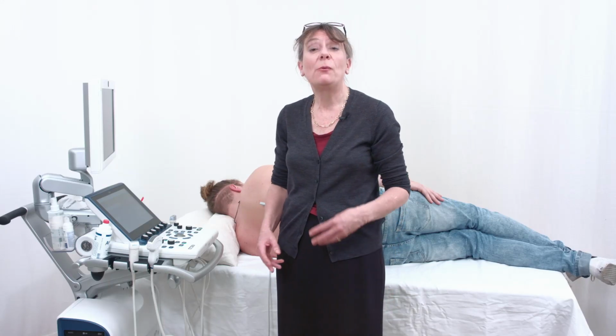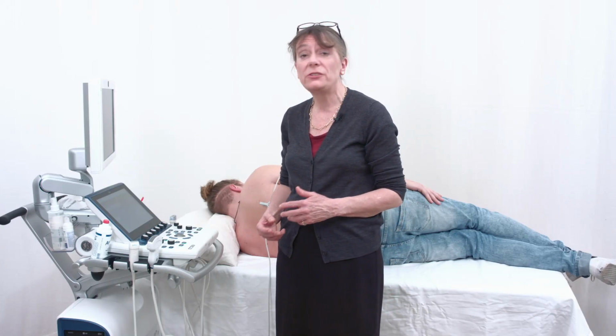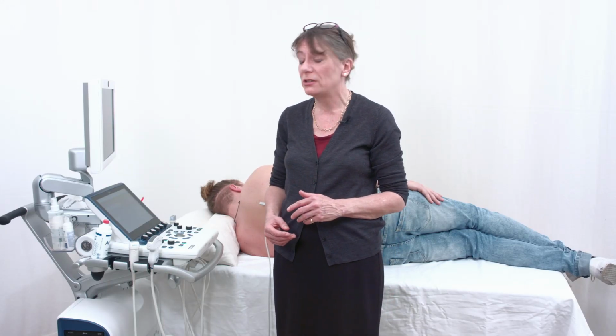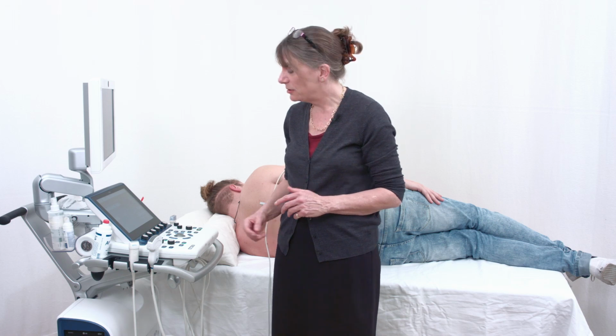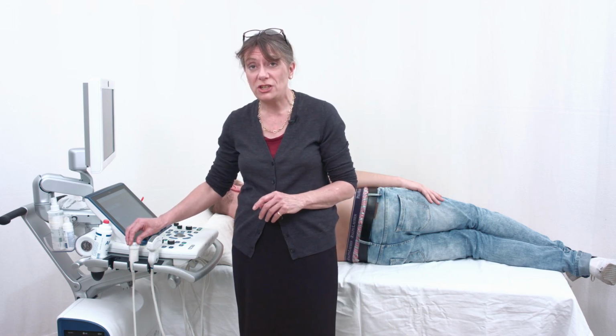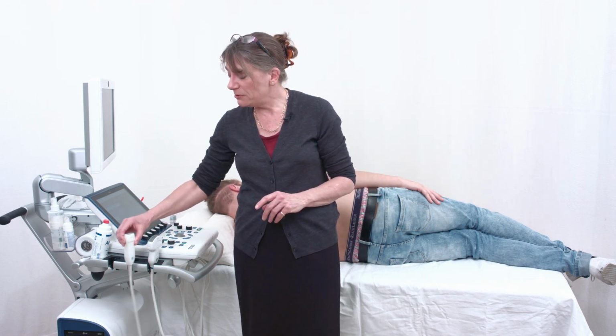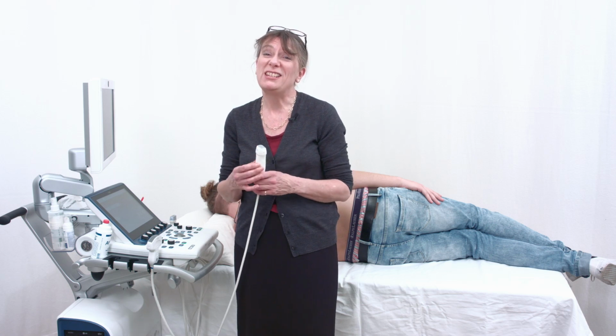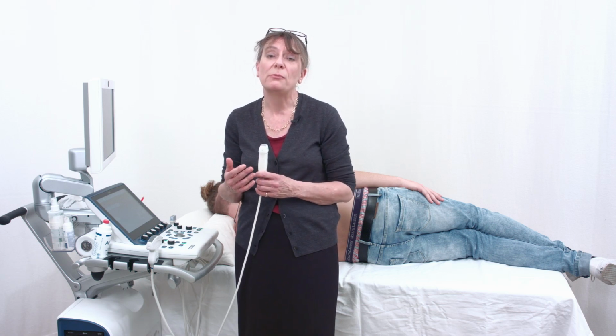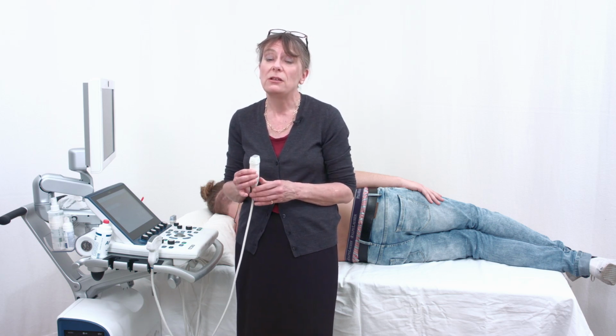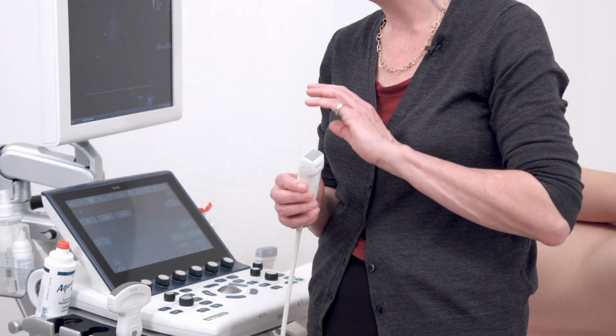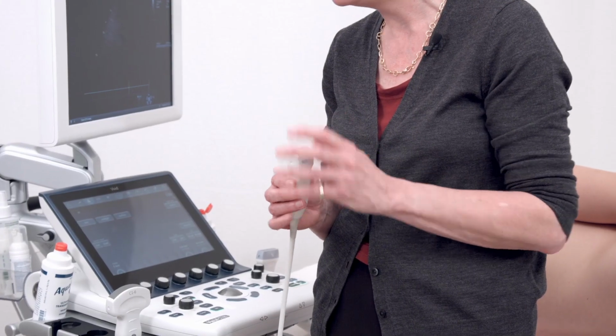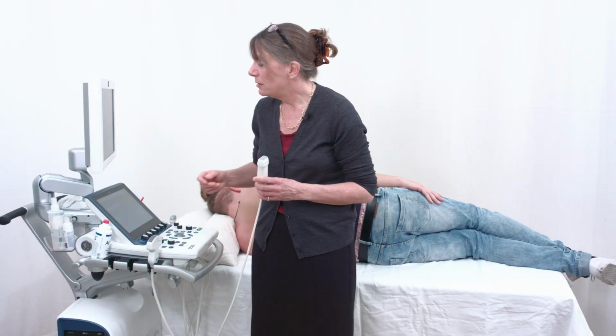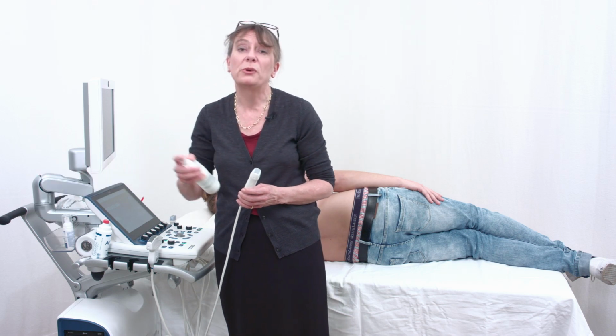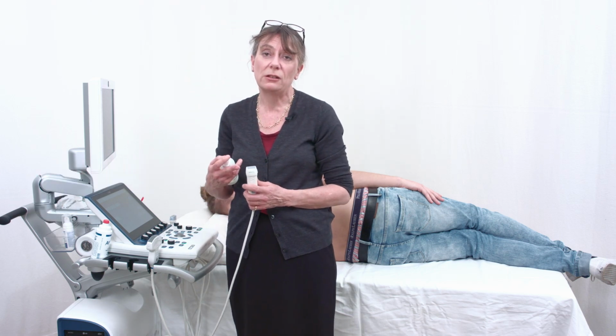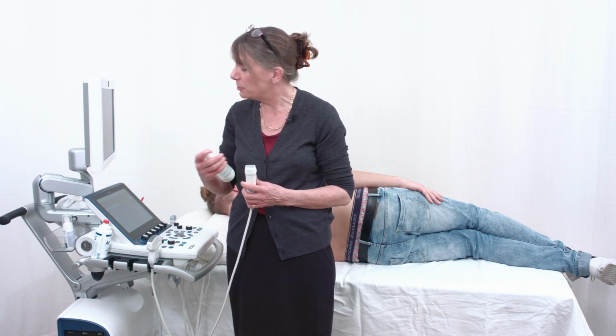We need to think about how we're going to keep our equipment clean. Obviously, things that actually touch the patient are most important to think about. So that will be the probe and the ECG cable. We need to be really careful with probes. They're very delicate, and you probably need to consult with your manufacturer to see what they recommend, so that you use an appropriate tissue to wipe off the gel at the end of the study, and then you clean it. There are special sprays to do this that are very gentle but still can make the probe safe.